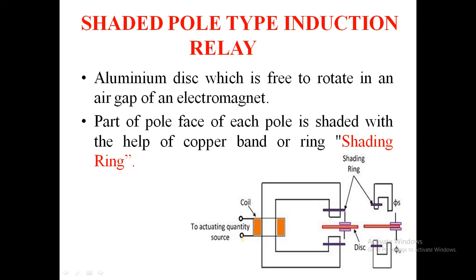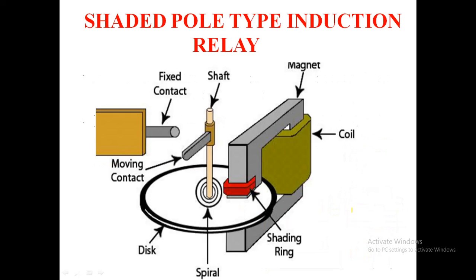The next type is the shaded pole type induction relay. In this relay, an aluminium disk is free to rotate in an air gap of an electromagnet. Here is the coil representation, the rotating disk, and the shading ring. A portion of each pole is shaded with the help of a copper band called a shading ring. The diagram shows the fixed contact, moving contact, disk, spiral, shading ring, copper band, coil, and magnet.